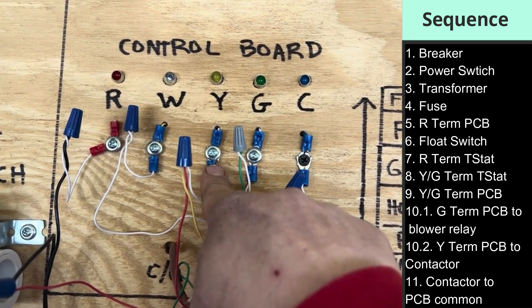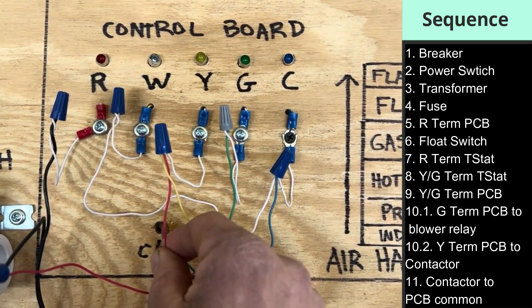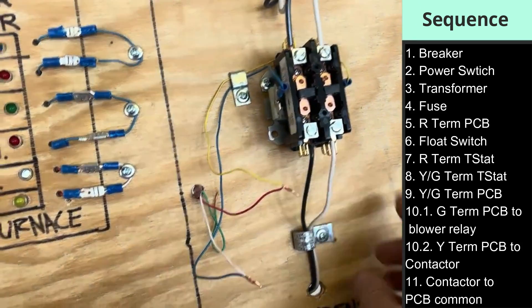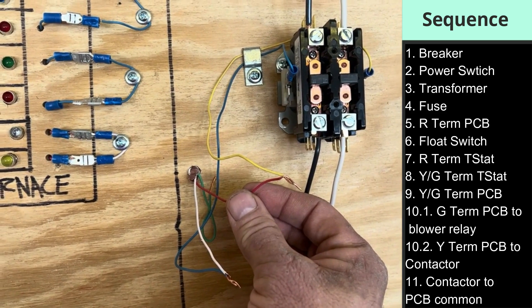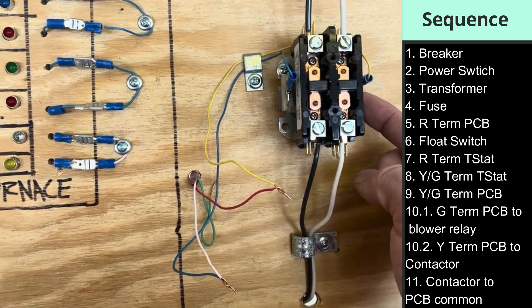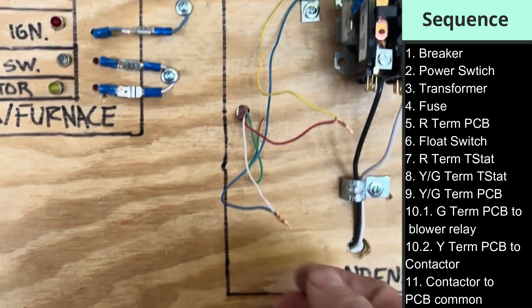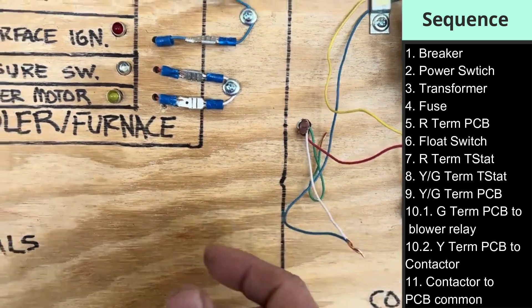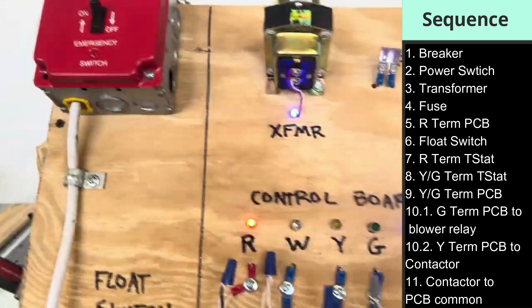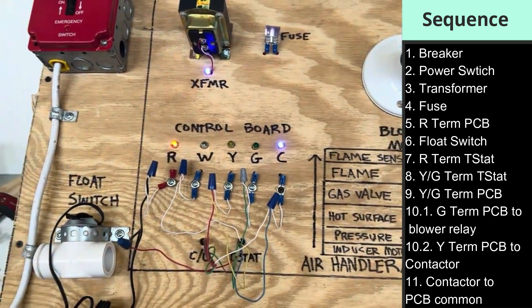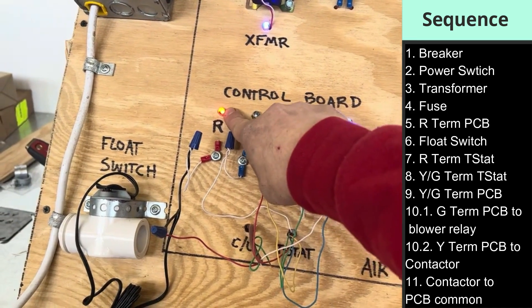If you have a control board, you'll usually see a yellow wire from your thermostat and a red wire that's a separate thermostat wire that travels along with your copper line set to the contactor outside. This takes the Y signal from your thermostat to your control board, sending that same 24 volts to the contactor — 24 volts through the contactor pulls it in and completes the circuit. We use a white wire as the common coming back to the common on the control board. Now I'm going to go ahead and turn the power on.